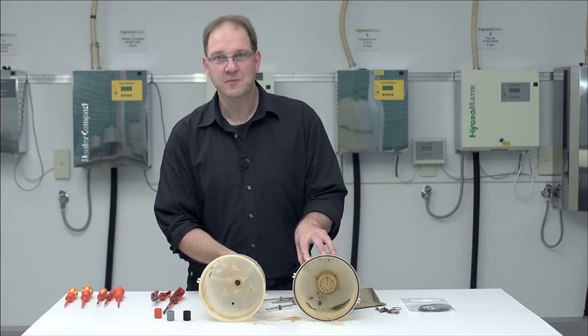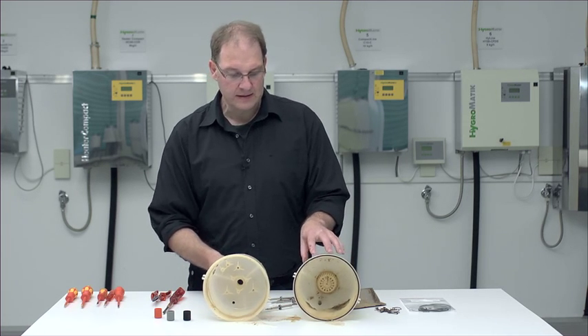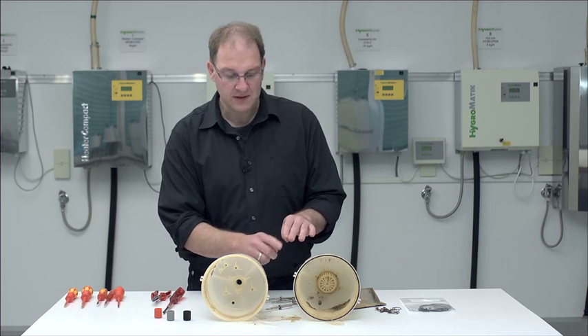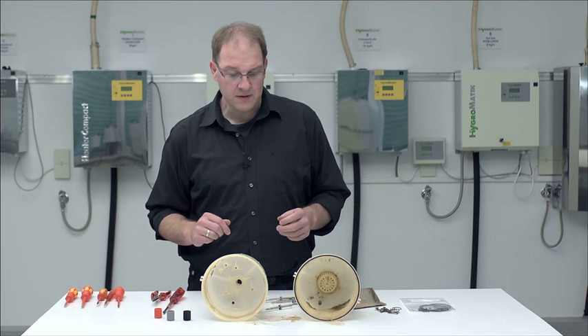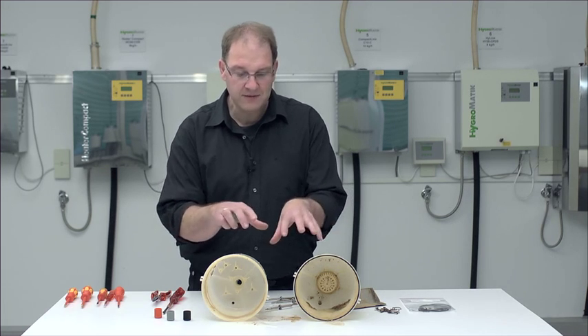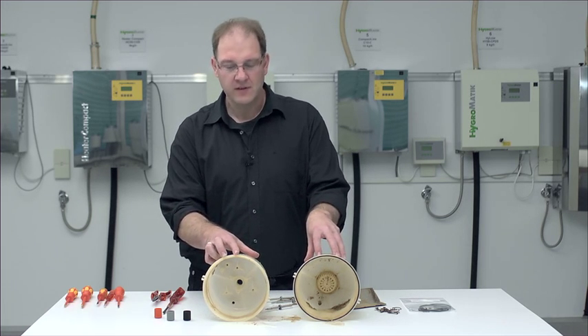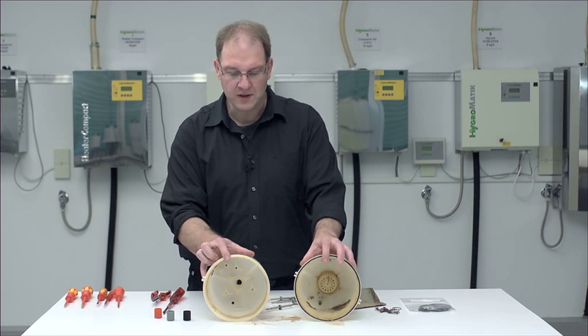When handling these electrode humidifiers, please don't use cleaning agents because the principle is to send an electric current through the water and it would be disruptive if we had any chemicals in the water because with them the generation of such a current would be severely disrupted.